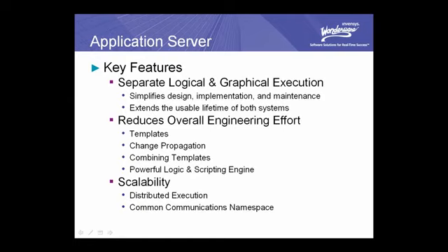You see, when you create instances from your templates, you also tell the system where these instances will be running or executing. It might be an HMI node or it might be a server without any HMI at all. The key here is that you decide where those elements will be executing their data acquisition, their scripting routines, their historization logic, and all that. If one machine happens to get overloaded with too much, you simply drag and drop the objects you want to another node.